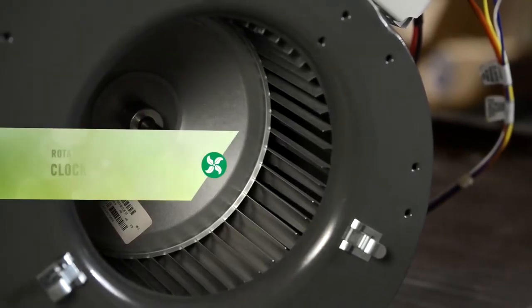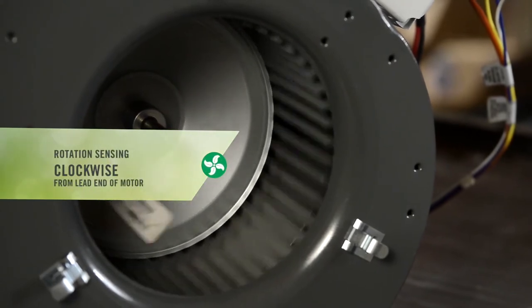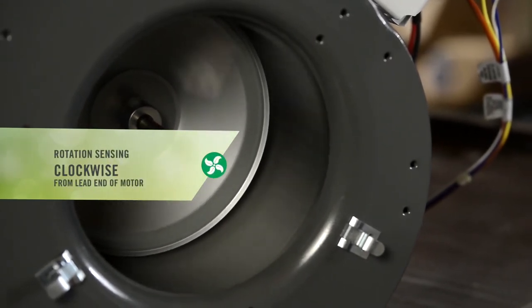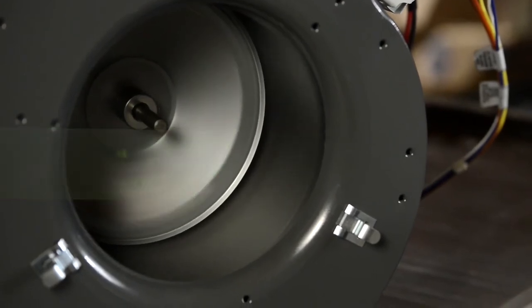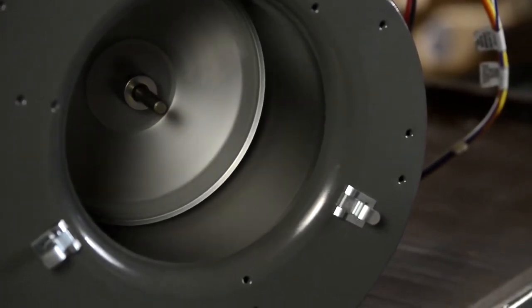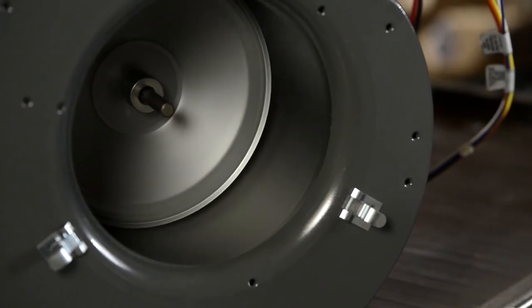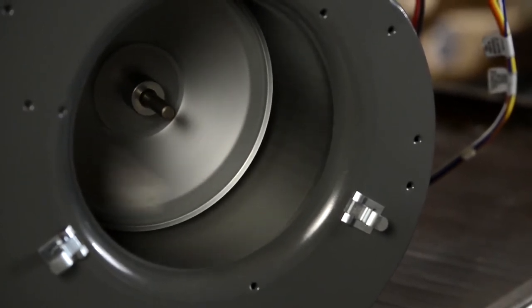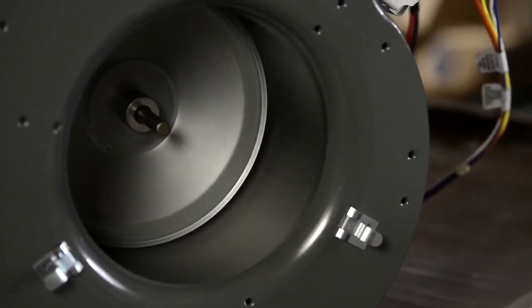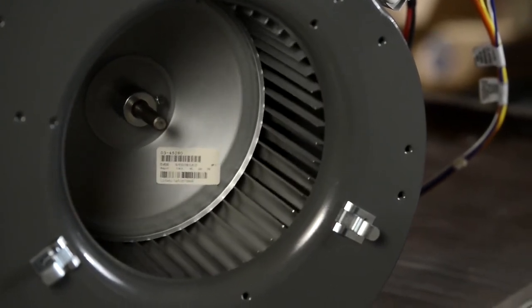So the first time the motor turns on, whether it's a heat call, fan call, or cool call, the motor is going to turn on and run about 10 to 15 seconds in the clockwise rotation. Now that may not be the rotation you need, and you'll notice that the motor is running fairly slow. It'll run for 10 to 15 seconds in this direction, then it'll slow down and stop, which is going to make you wonder what the motor is doing.